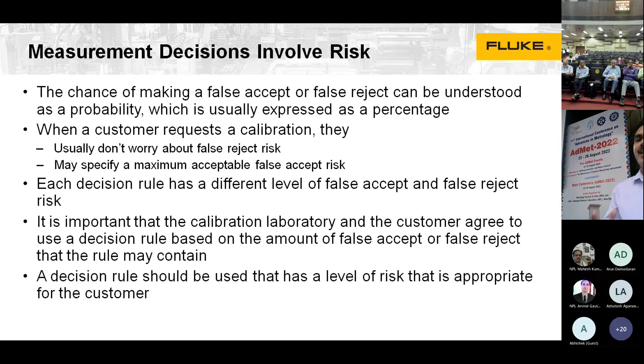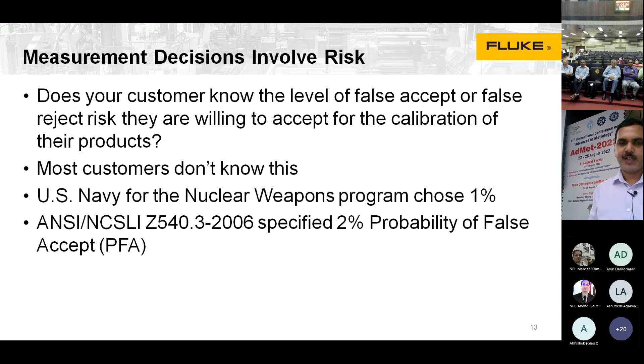So does your customer know the level of false accept or false reject risk they are willing to accept for the calibration of their products? The answer is, most customers don't know this. So the US Navy, for the nuclear weapons program, chose 1% as tolerance, whereas ANSI or NCSLI specify a 2% probability of false accept, or PFA. So it is good to understand what your customer does, to understand what level of risk they can tolerate.